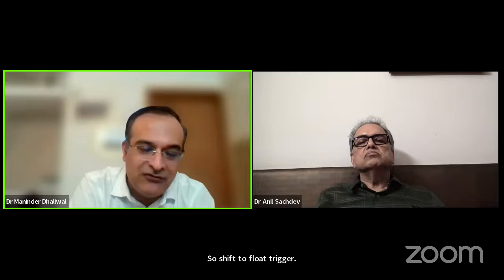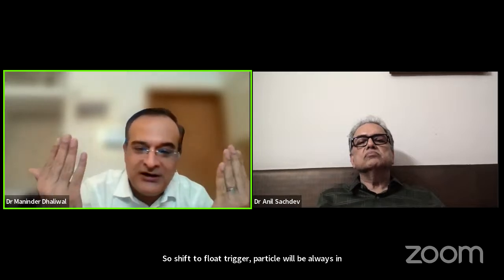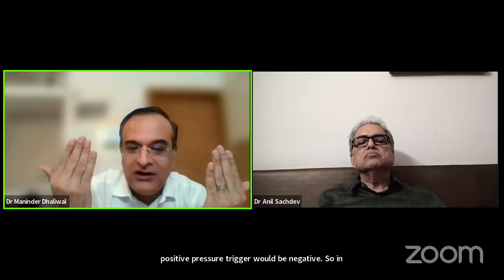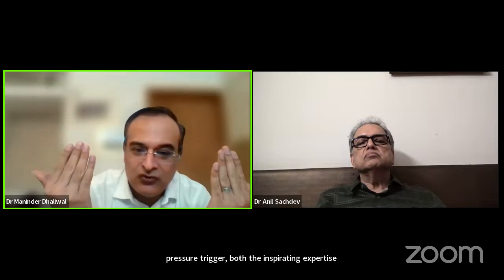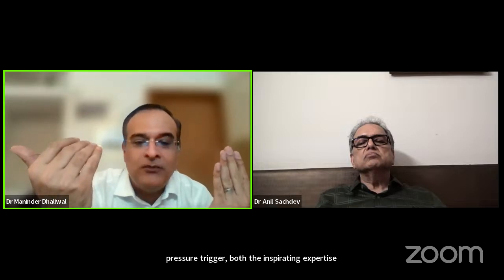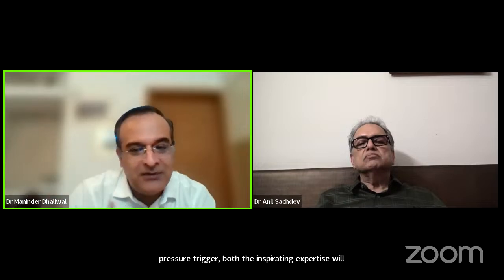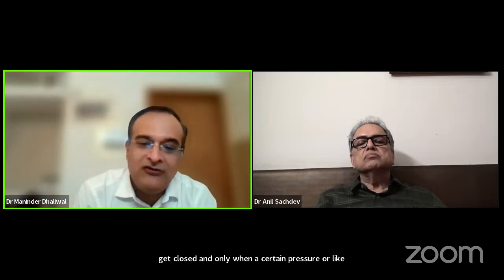Pressure trigger would be in negative. In pressure trigger, both the inspiratory and expiratory valve will get closed, and only when a certain pressure, like -2, then only the inspiratory valve will open. But in that millisecond, the patient will have a flow starvation, and it's not good. So we have moved away from pressure trigger.